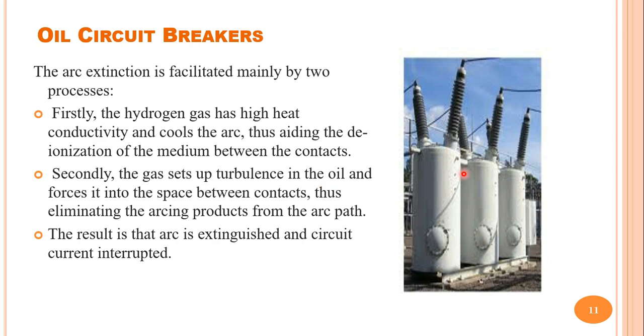In an oil circuit breaker, there is a chamber filled with oil and the moving contact and fixed contacts are placed in the chamber. When the moving contact is separated from the fixed contact, the arc is formed between the contacts in the oil present in the tank. When the oil is heated up, hydrogen gas is produced in the tank. The hydrogen gas has high heat conductivity and cools the arc, aiding the deionization of the medium between the contacts and helping arc extinction.